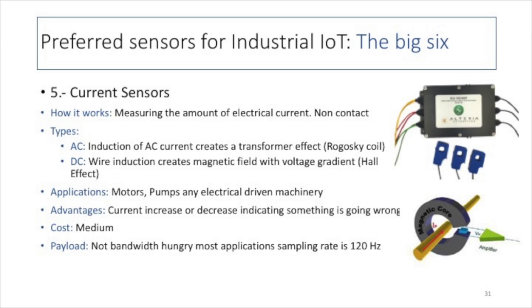There are different technologies to monitor the current drawn by circuits or machinery, depending on whether you are monitoring AC or DC. We use different transducers. Rogowski coils are used in AC, while in DC we use Hall effect sensors. You can make good use of a current sensor, monitoring the current drawn by pumps, motors, and rotating machinery in general. It's a very interesting parameter and a good complement to other sensor measurements. The cost is medium to low, depending on the application. They are not especially bandwidth hungry.